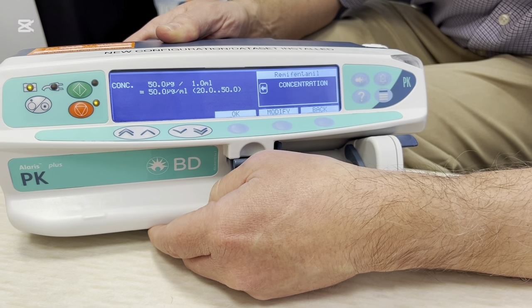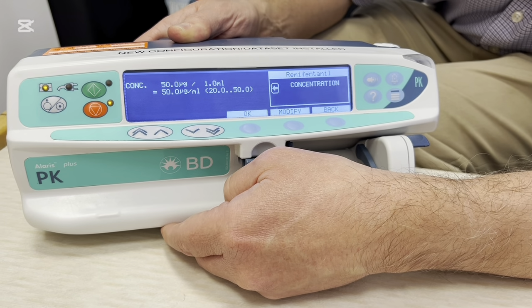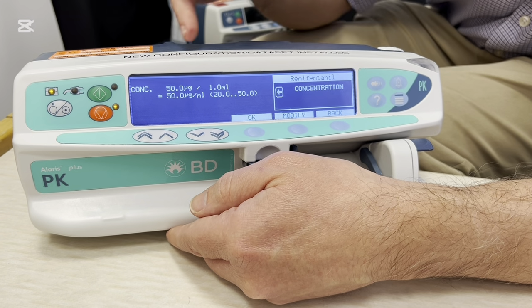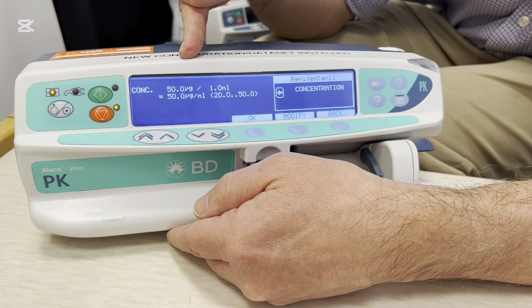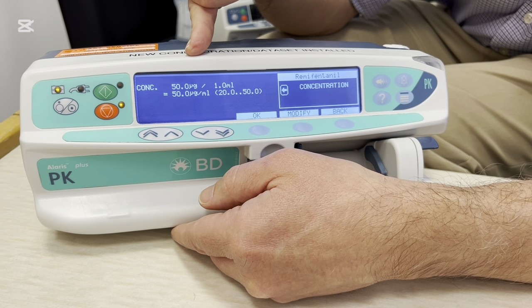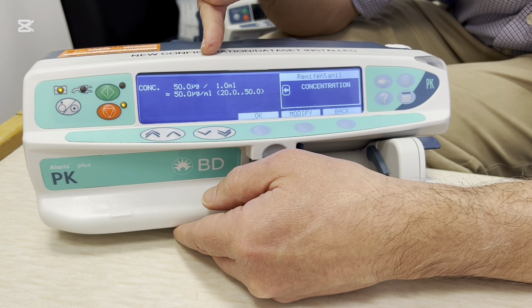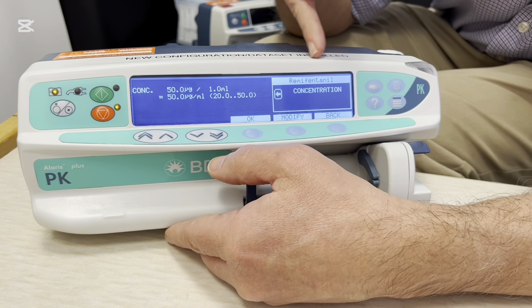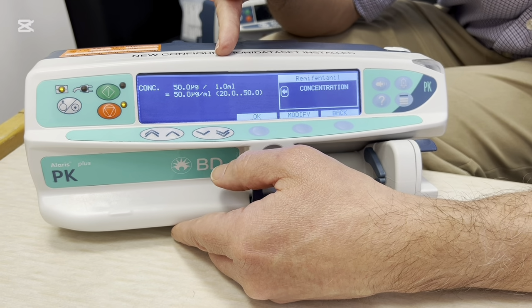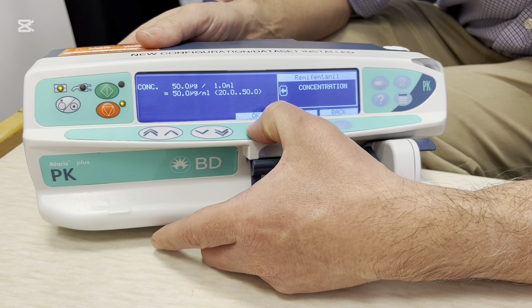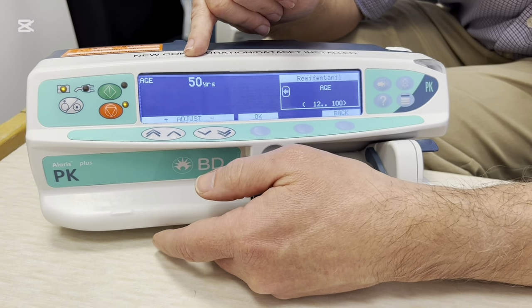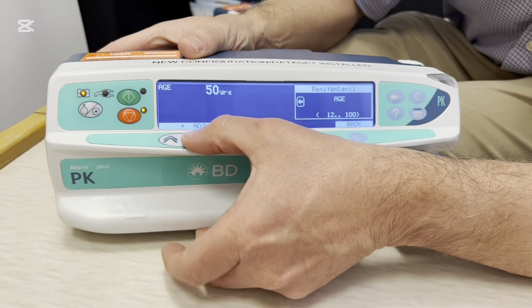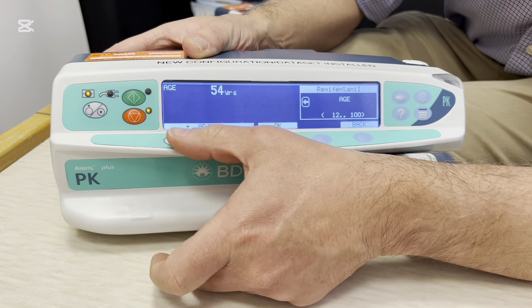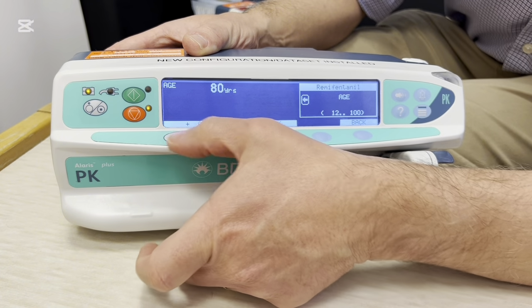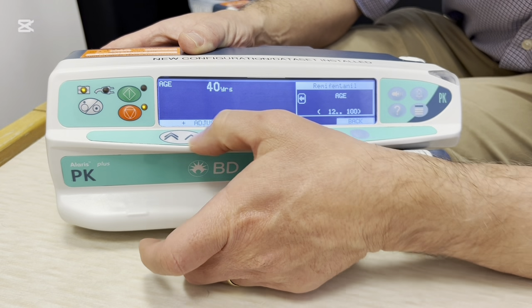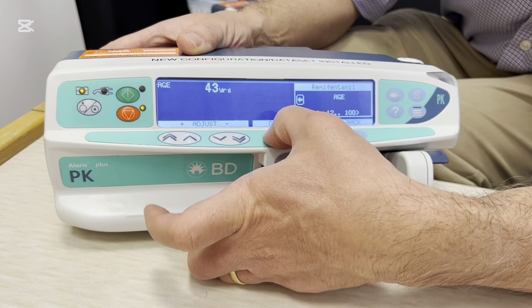And now to enable this pump to deliver the drug in the desired way, it's going to ask you a number of questions. So it's going to ask you about the dose. So check that you're actually making up your remifentanil solution to the solution that it recognises up here. If not, then adjust the concentration accordingly. But I think the standard is for 50 microgram per mil infusion. So we'll confirm that's OK. Enter the patient's age, and you can adjust the patient's age with the up and down arrow keys. You can just leapfrog with the big arrows. I'm going to press OK.